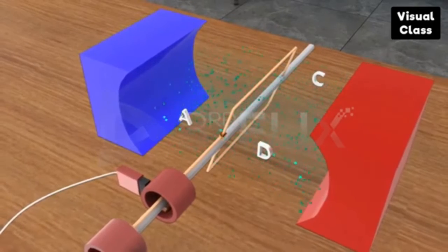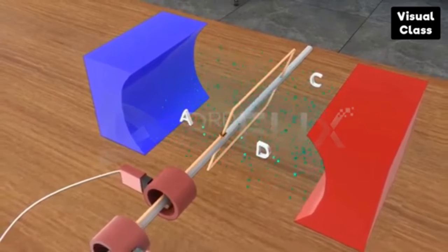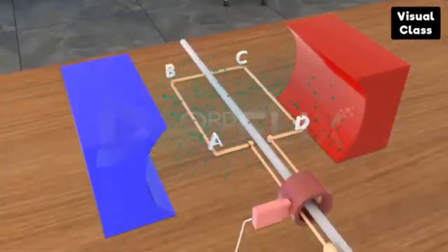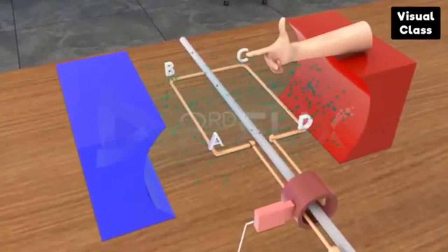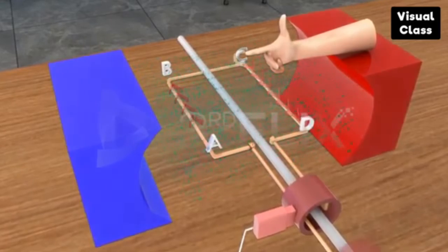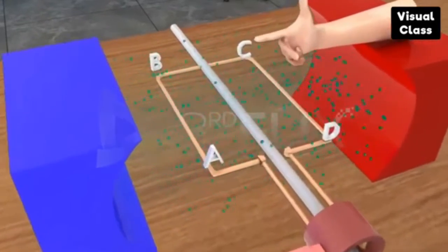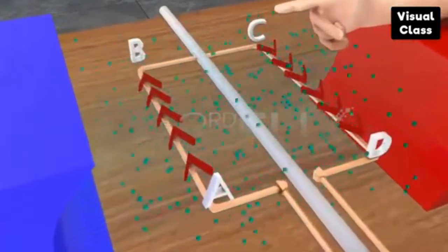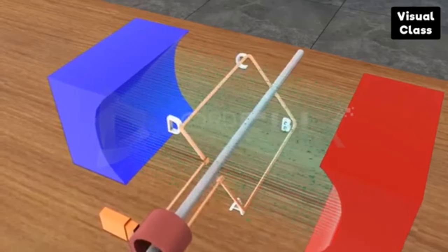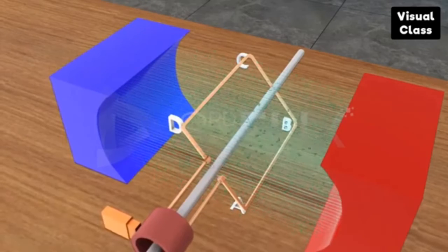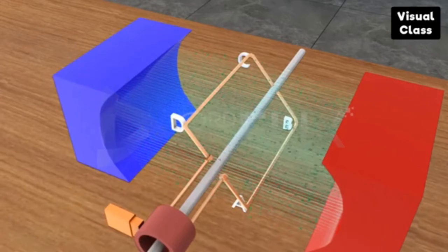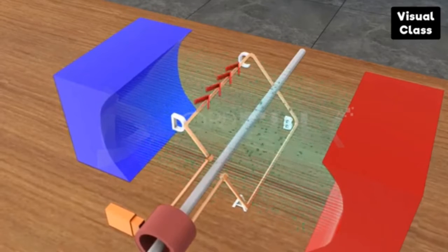The motor casing supports the stator and other motor components, as well as protects the stator and rotor components from the external environment. Normally, they are made of steel. Commutating brushes are used to supply electricity into the rotor. It maintains contact with the commutator regardless of the speed of rotation, and contact pressure is maintained with the help of a spring. The operating power is supplied to motors through their terminals.